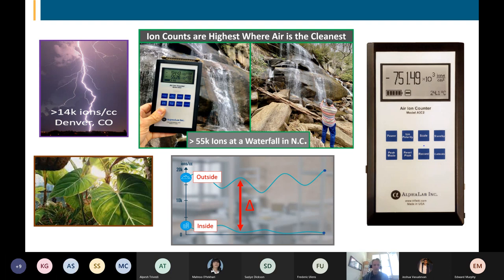What we are doing with bipolar ionization is simply imparting an artificial charge of energy to the atoms and molecules in the air that cross over the device, go out through the HVAC system into the space itself, to try to create ion concentrations in the space that are at a closer level to those outdoors where the air is cleaner. It's that simple. It's a very simple concept. And that's what I'll talk about moving forward. Any questions on that?